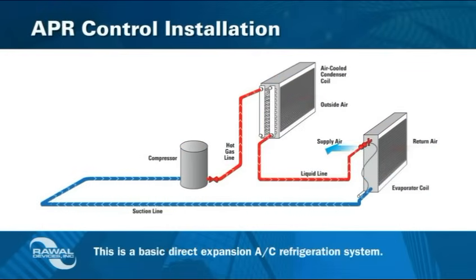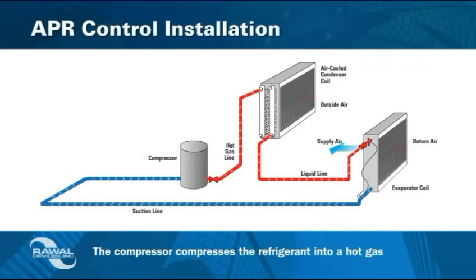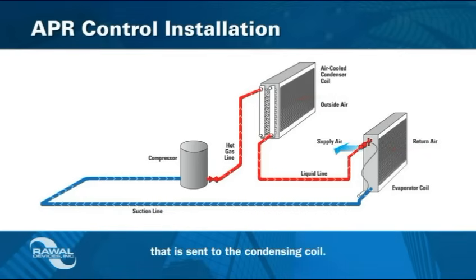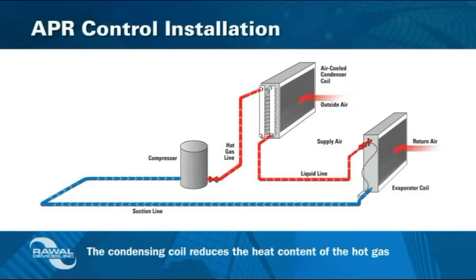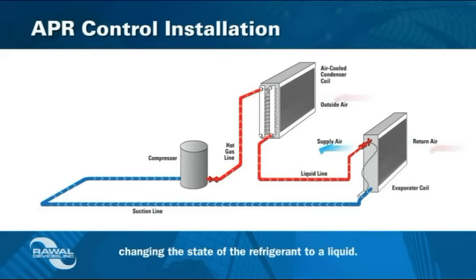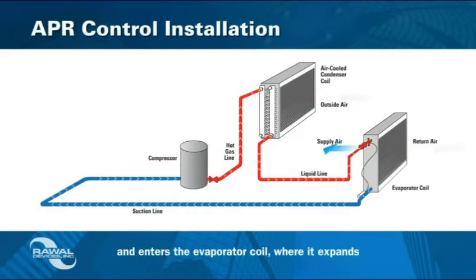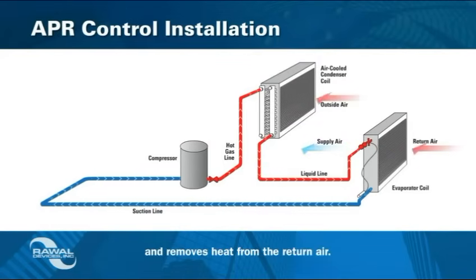This is a basic direct expansion AC refrigeration system. The compressor compresses the refrigerant into a hot gas that is sent to the condensing coil. The condensing coil reduces the heat content of the hot gas, changing the state of the refrigerant to a liquid. The liquid passes through the expansion valve and enters the evaporator coil, where it expands and removes heat from the return air.